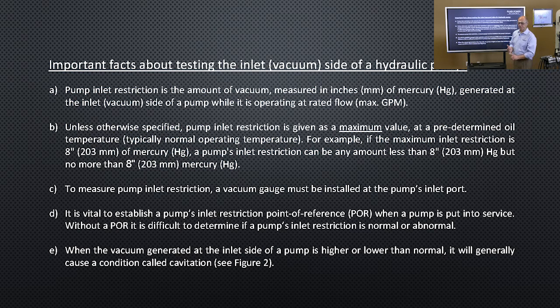Number two, manufacturers and hydraulic system designers have inadvertently, it seems, given the information that is for their consumption, meaning the manufacturer of the pump's maximum inlet restrictions, and they've passed it through to maintenance. That's not the information maintenance people need.